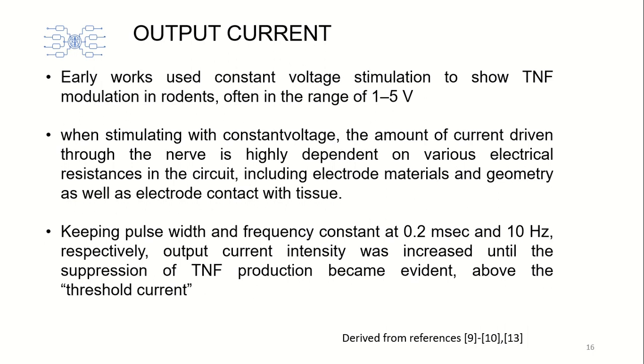However, when stimulating with constant voltage, the amount of current driven through the nerves is highly dependent on various electrical resistances in the circuit, including the electrode material and geometry as well as electrode contact with the tissue. Although somewhat controllable in the laboratory, it is well known that impedances of implanted electrodes change over time because of tissue remodeling and electrode surface electrochemical changes.